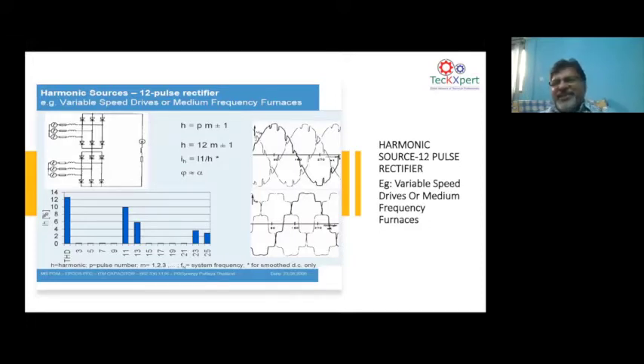11th and 13th, the magnitude can be smaller. 23rd and 25th, again fine, the magnitude can be smaller. But what happens in a power system is that if you have these resonating frequencies in the network, sometimes these resonances can get amplified by an external transient. It can happen that you have an oscillatory transient in voltage coming into your factory or to your building, traveling from a BESCOM network.